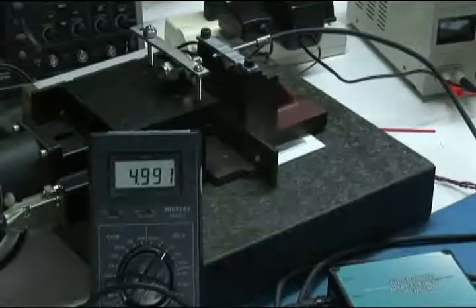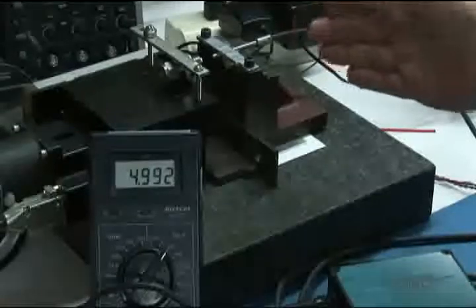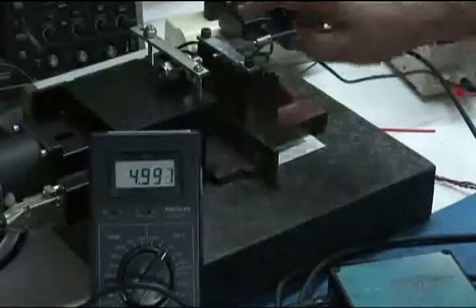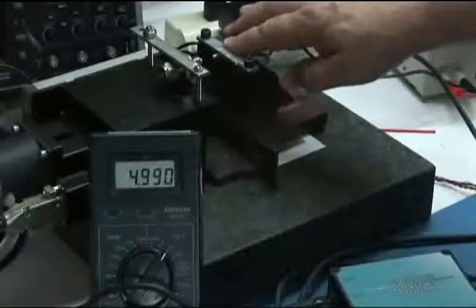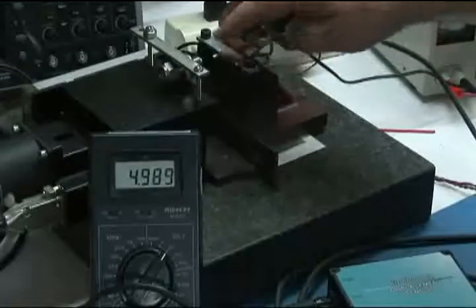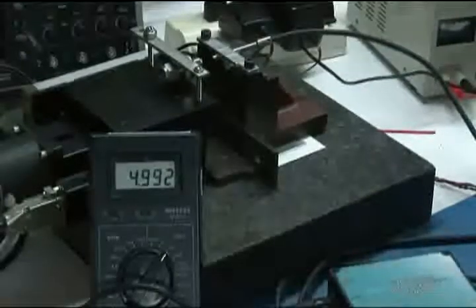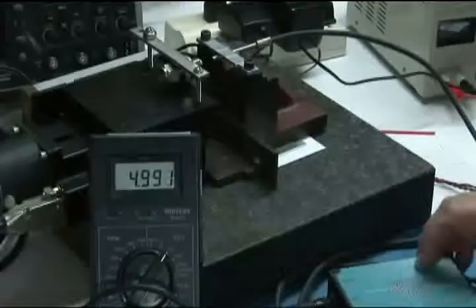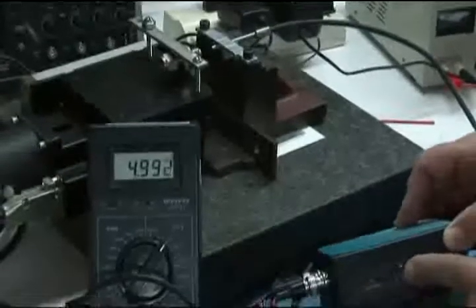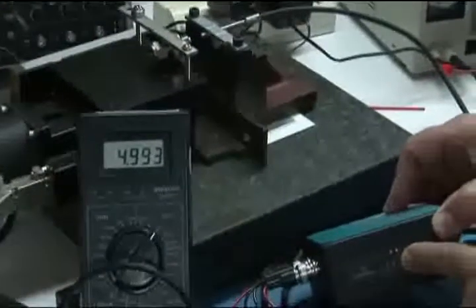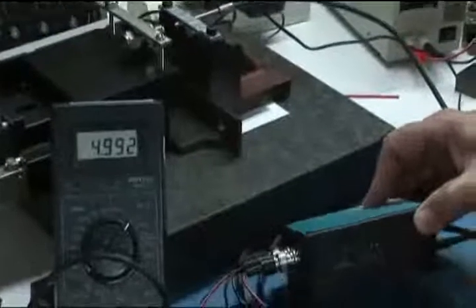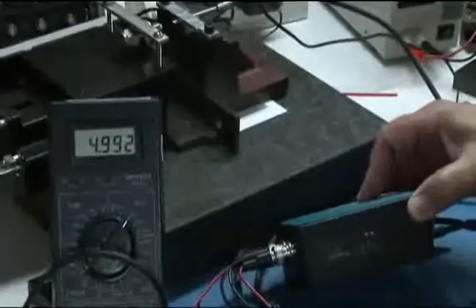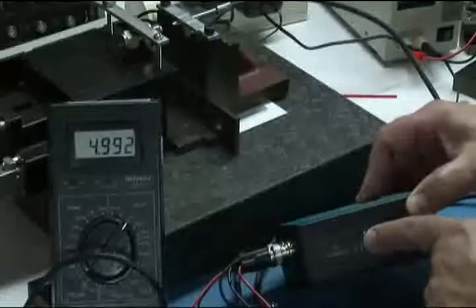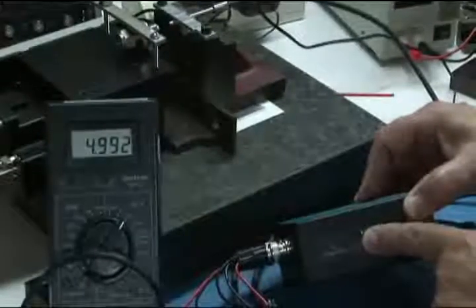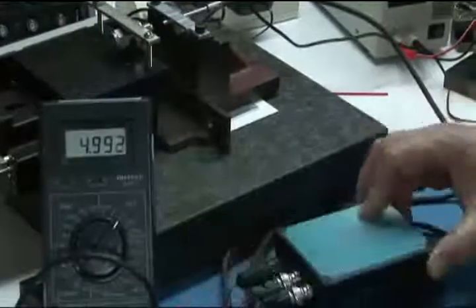So I think the best thing for you to do is to go through this procedure where you install your sensor at each pin location, bring it into contact, then move a half inch away, and use this Cal 1 control to set the output to exactly 5 volts, as close to 5 volts as you can get it. And then you'll be good to go. The SNR control has already been set up for all your sensors. You shouldn't have to make any adjustments.